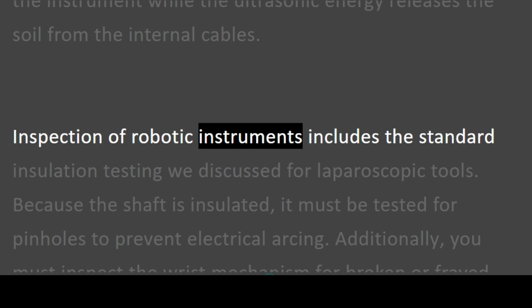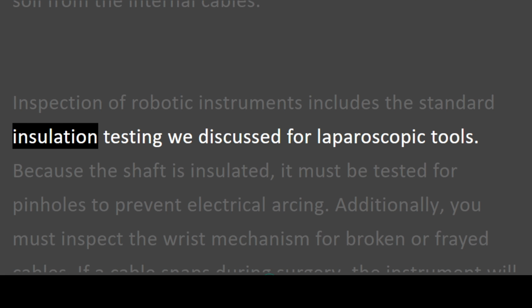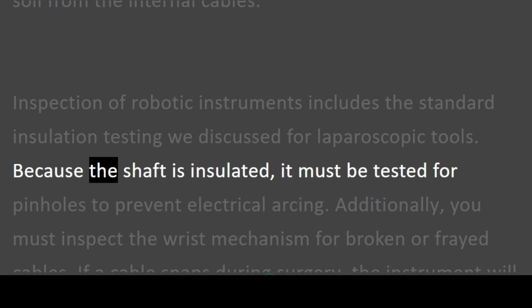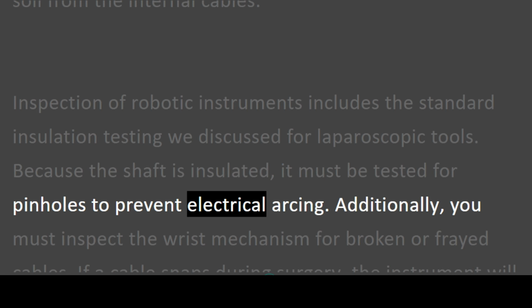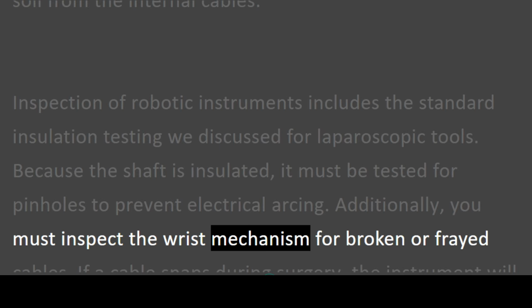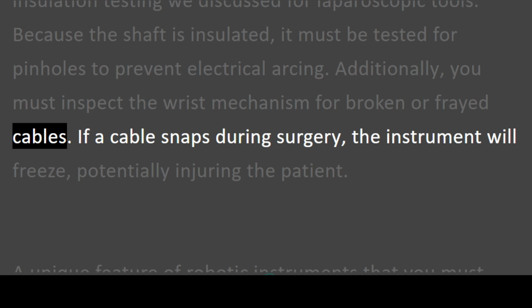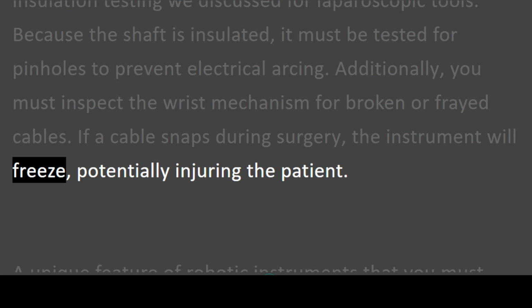Inspection of robotic instruments includes the standard insulation testing we discussed for laparoscopic tools. Because the shaft is insulated, it must be tested for pinholes to prevent electrical arcing. Additionally, you must inspect the wrist mechanism for broken or frayed cables. If a cable snaps during surgery, the instrument will freeze, potentially injuring the patient.